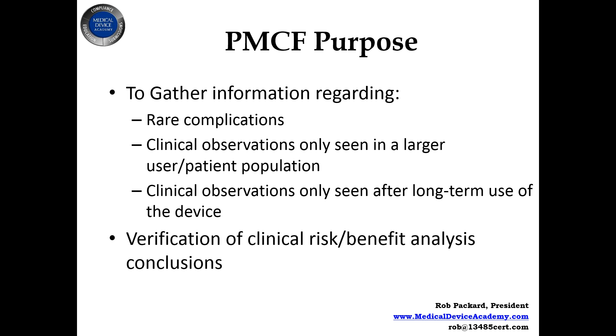This next slide shows people what post-market clinical follow-up is and what the purpose is. I indicated in these three bullets what are some of the primary reasons why you're conducting post-market clinical follow-up studies: to look at rare complications that you couldn't capture in a small clinical study, to look at things only seen in a larger user or patient population, and to look at things that are only seen after long-term use. You're not going to do a 20-year clinical study before launching a product.